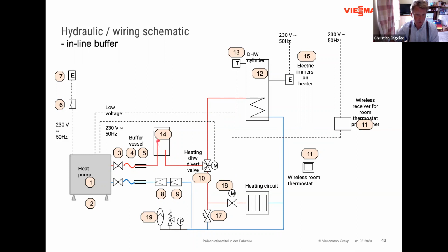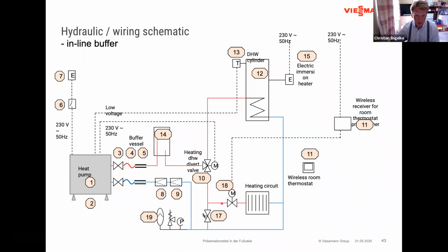In this case, it's from Viessmann, a 45 liter space-saving wall-mounted unit that can be used. You can use some other means as well, but it's important that the water volume in the pipes is considered at least 50 liters. And I said last time, the water volume in radiators is not to be counted, only the water volume all the way up to the nearest two-port valve, actuator valves or TRVs fitted in the heating system.